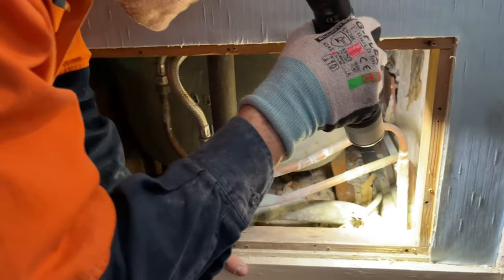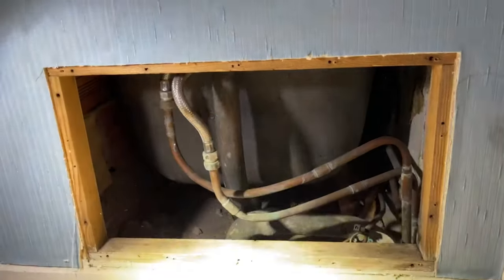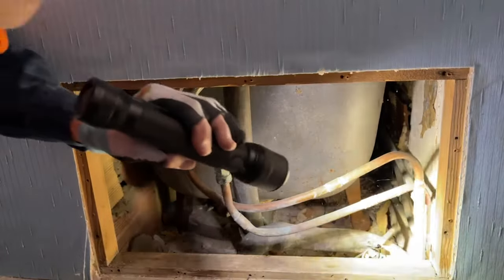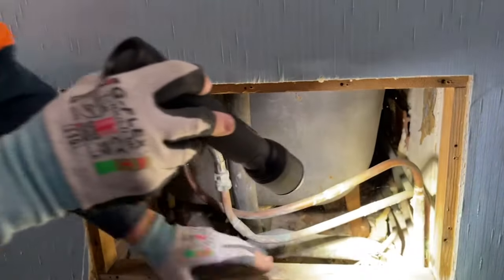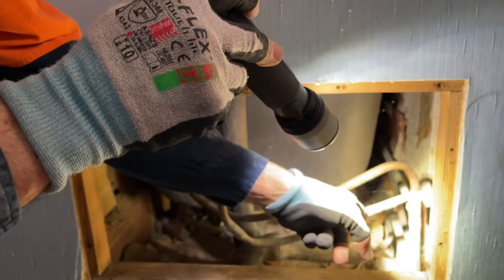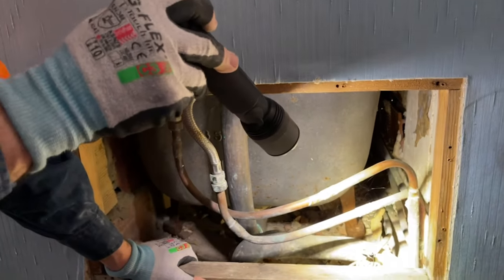Where's the mirror? So you're just doing testing? No, we're trying to find cabling. Just trying to get back. We're trying to trace it. We found one of the cables goes through the wall in the bathtub, but to see how it's sitting, so you don't have flex sitting on copper piping or anything like that. It's all got to be mechanically protected.